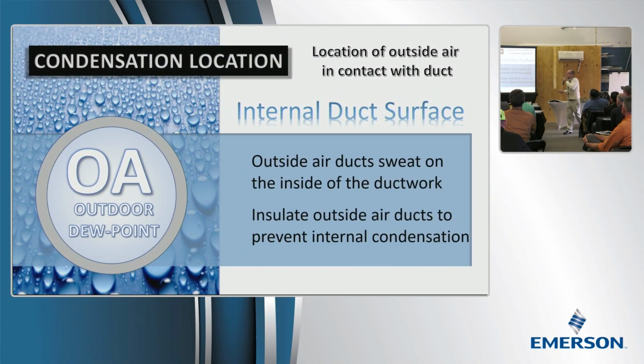In closing, we'll mention that when ducts sweat on the inside, it's the exact opposite — that happens from infiltration, backdraft, backwards through ventilation. So the clothes dryer is intended to vent out, but the wind's blowing it back through, the backdraft damper's stuck open, and you get wet. Same thing with the bath fan — outside air hits the inside, so the inside gets wet. It works the same way, it's just that the duct is getting wet on the inside.